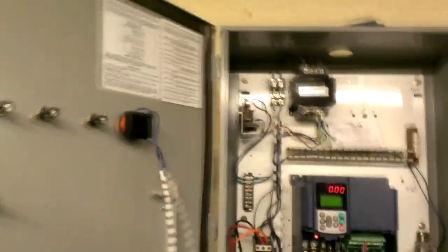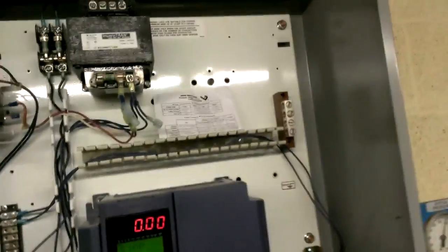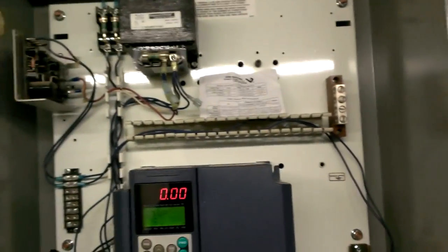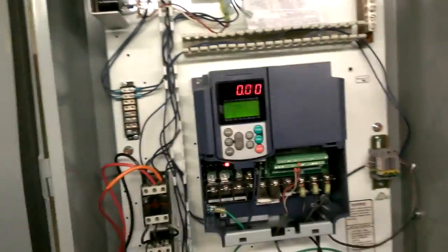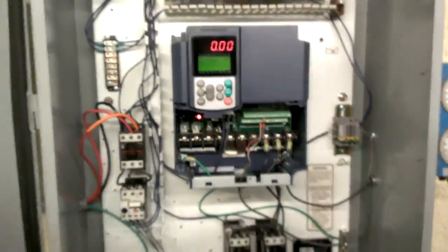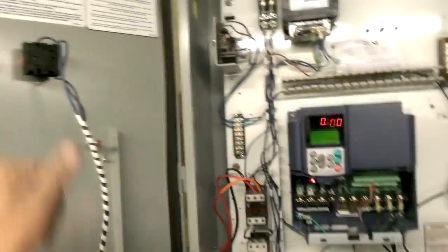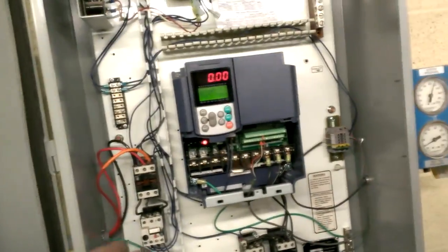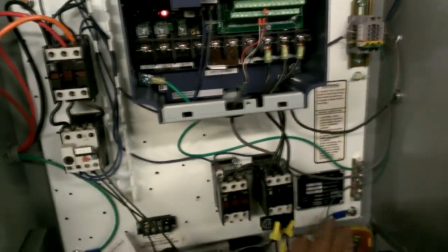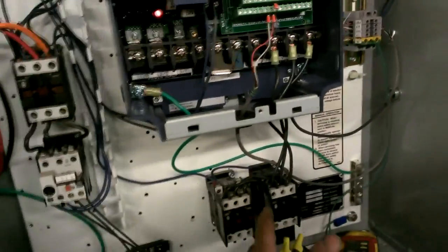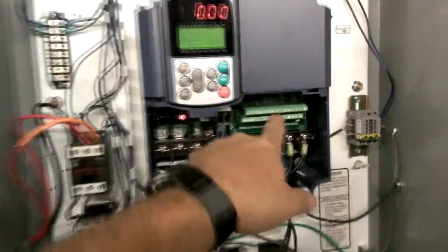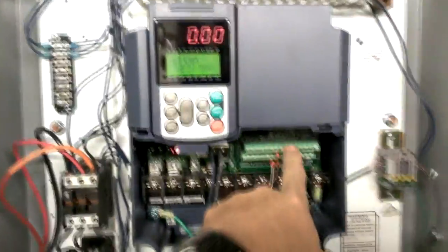I've decided to make my own control. I've disconnected this switch out here, which is labeled F1 and F2 now, and off. It's gonna go just 5-volt logic, going to a microprocessor control now that I'm gonna build. Put it on a little circuit board up here. And basically, it's gonna run the command. It's gonna have some logic. Basically, when you call for a pump, you're just gonna flip that on. And it's gonna first pull in the contactor for whichever pump, one or two. And then it's gonna give the command for this to start.